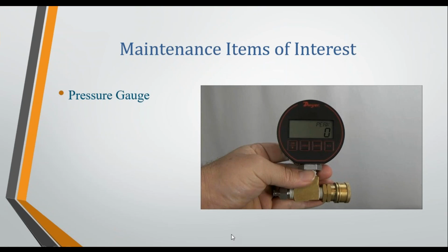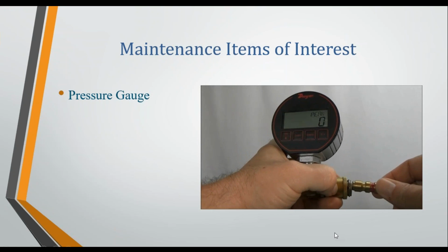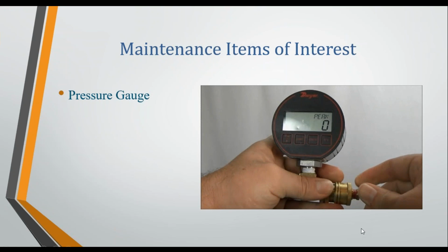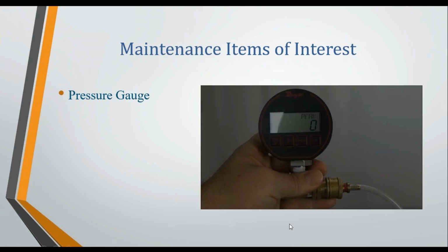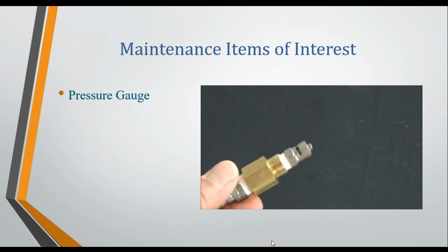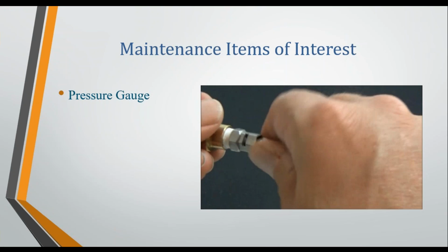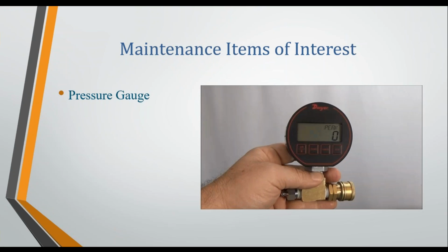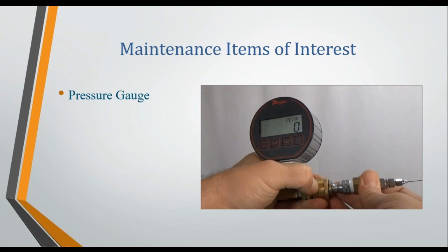A lot of times when people say, oh, we already have a pressure gauge, well, I know every biomed shop has a pressure gauge, but do you have a pressure gauge that can attach directly to a syringe and is capable of measuring 1,000 PSI without blowing off? Typically, the answer to that question is no. That's what this down here is for, connected to the pressure gauge, and then our connector here is for the special orifice. This red orifice that I'm connecting to it is specially made to measure specific pressures on the injectors. And if we don't use the orifice, then we use a 20, 21, or 24 gauge needle, depending on the machine, to do the same thing the red orifice does, and that's measure a specific pressure during a specific flow rate through the pressure gauge.